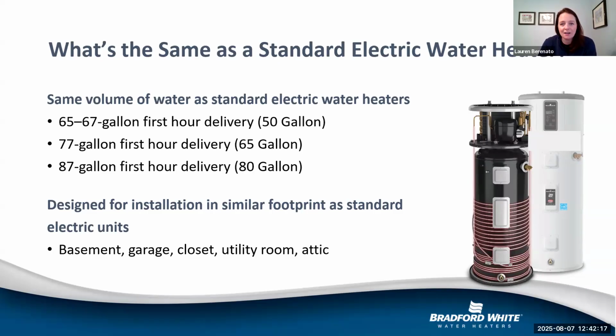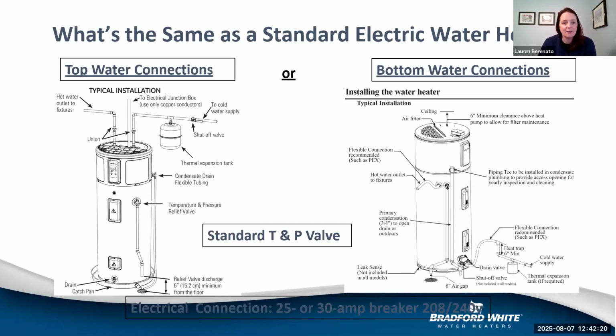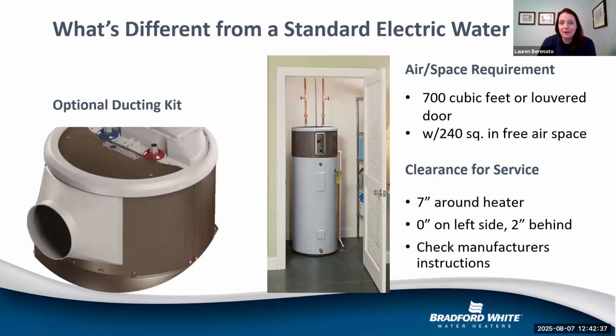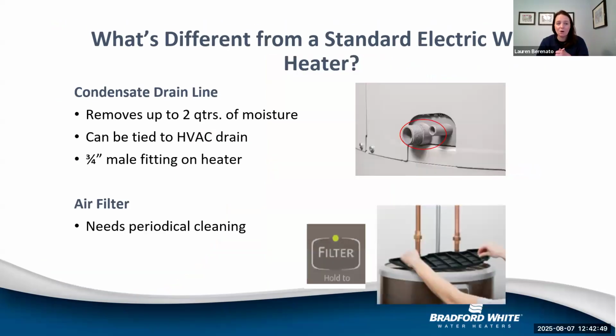These next couple slides just show you the differences and the similarities in the physical setup between the heat pump water heaters and the standard electric. You can take this information off of the unique specification sheets, based on what you're specifying. Again, airspace requirement was never really a consideration before for standard electric. Clearance for service, again, look at your installation manuals and your specification sheets to see where that will come into play. Again, more questions about this.